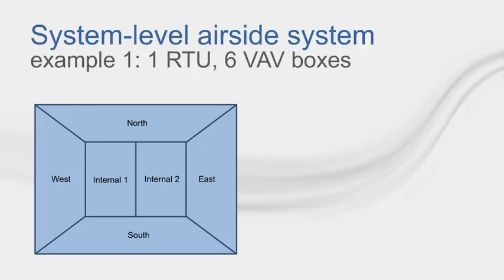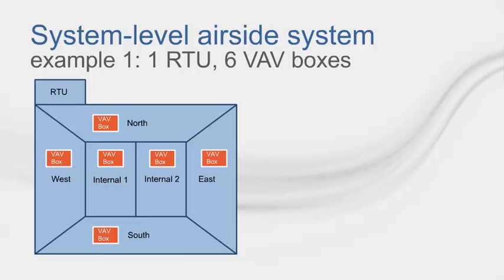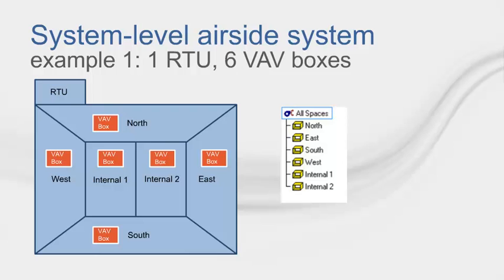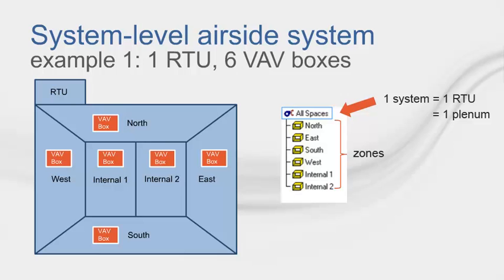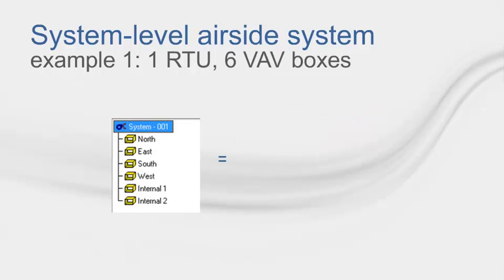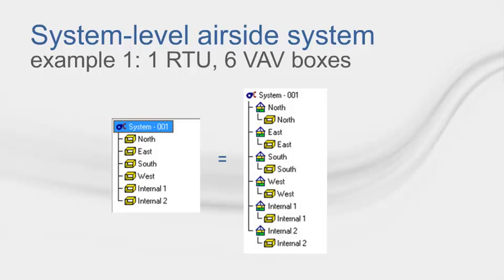In this example, we want one rooftop unit and every room to receive a VAV box. In TRACE, this would look something like this. I have one system, so one RTU and one plenum. I have six zones, so six VAV boxes. You may notice that I have six rooms, not six zones. But in TRACE, any room placed directly under a system is considered a zone — having a room directly under the system is just like having a zone with one room under it.